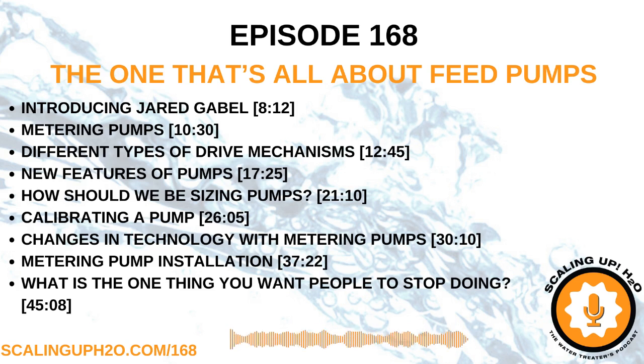So we're already using a drive now because we're able to take the speed of that motor and adjust it depending on the suction and discharge phase. And we don't necessarily need a static mixer because we're blending it. We're always injecting chemistry in instead of pulsing it in and then waiting and slug feeding. So anytime you have a slug feeding application where it's just injecting with a suction and discharge, then waiting a period of time, then you're not getting a really good blend.